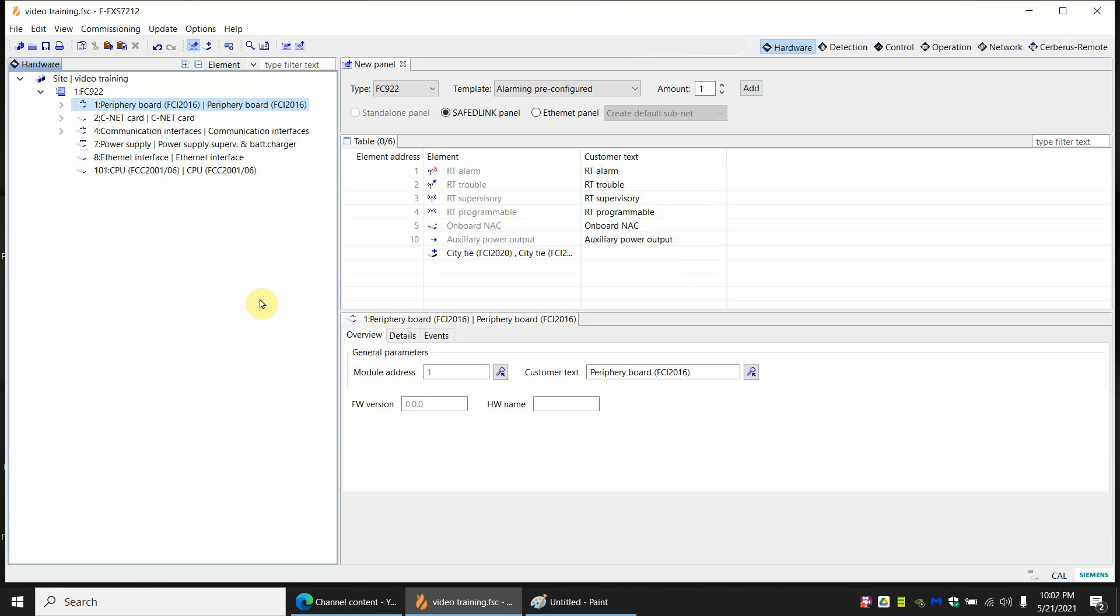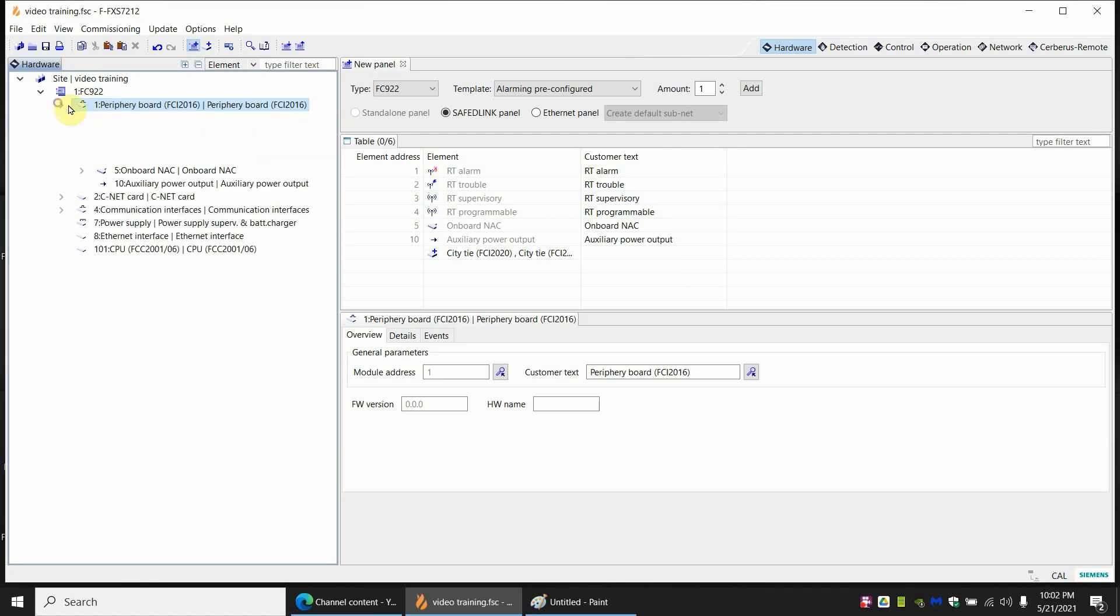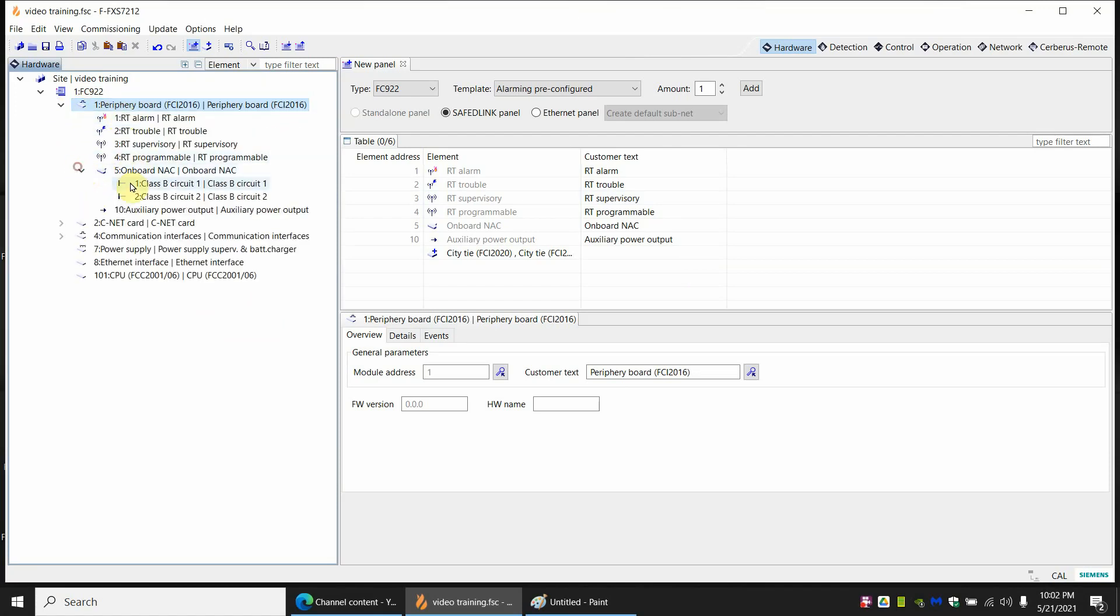So to start us off we're going to add an additional NAC board. By default the 922 or 924 comes with two NAC circuits. It has an optional board to add two more NAC circuits. That's hooked up to the peripheral board. If you open up you can see the onboard NAC with the two NAC circuits. If you right click on the peripheral board and hit new you can see the options. On the board you can add a city tie, a lease line, and there's an optional NAC.